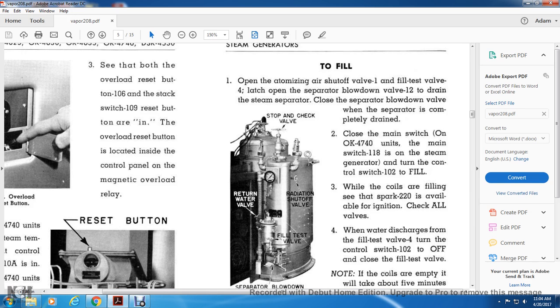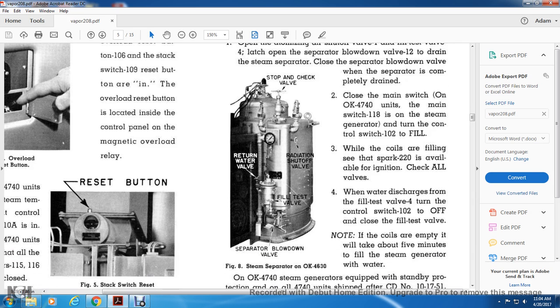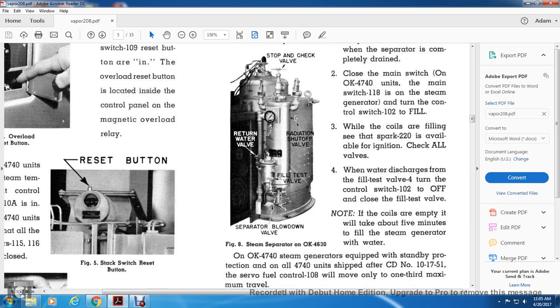Check all the valves. 4. When water discharges from the fill test valve 4, turn the control switch 102 to off and close the fill test valve. Note that if the coils are empty, it will take about 5 minutes to fill the steam generator with water. Figure 8 shows the steam separator, OK4630 model. From the top, you have the stop and check valve, return water valve, radiation shutoff valve, the fill test valve, and the separator blowdown valve.